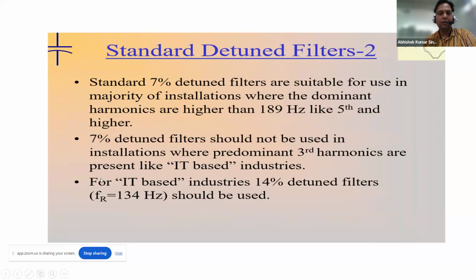So you can see here for IT-based industries, 14% detuned filter. This is basically 134 hertz. So any frequency which is more than 134 hertz can be suppressed by a 14% detuned filter. Whenever you are going to design your system, you have to take care of how much load is single phase load. If there is a lot of single phase load, then definitely you have to plan for a 14% detuned filter.